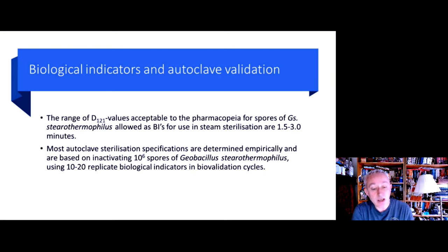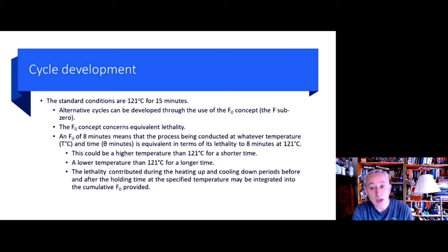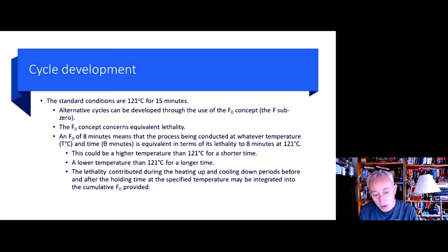We also have another concept that we need to consider for when we're doing autoclave cycle development, and this is the F concept. In particular, something called F sub zero, which is normally written with a capital F and a lowercase zero. This concerns equivalent lethality. The origin of this term dates back to the food canning industry in the 1960s. F sub zero is always linked to 121 degrees Celsius. It allows us to consider at what temperature, other than 121 degrees, and for how long, would deliver the same level of lethality, achieving this 1 million cell or spore reduction.